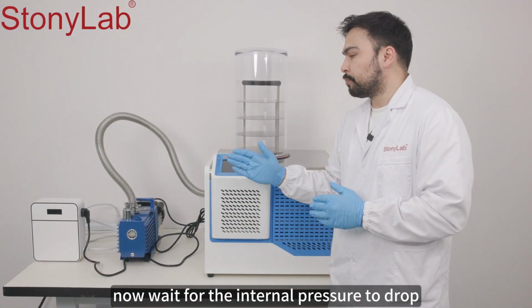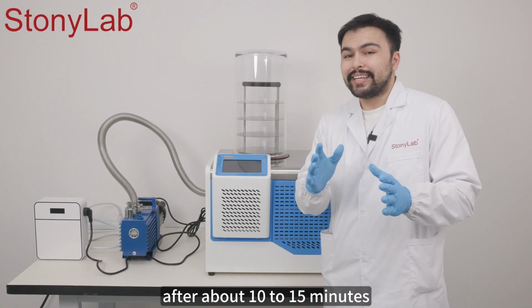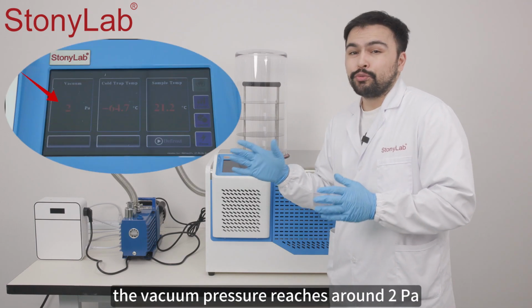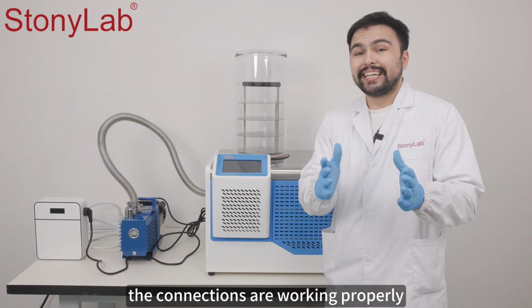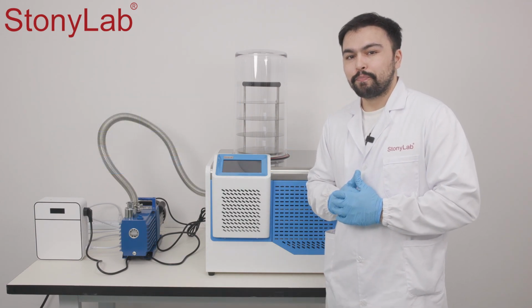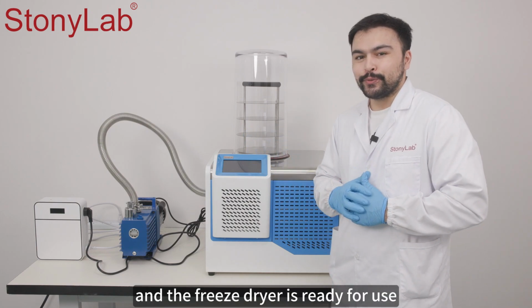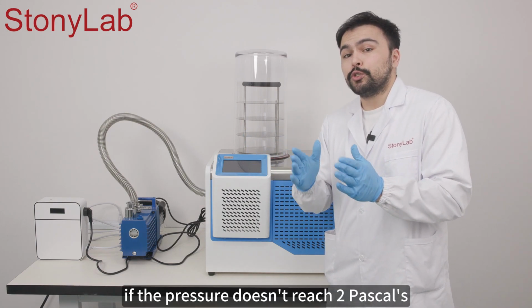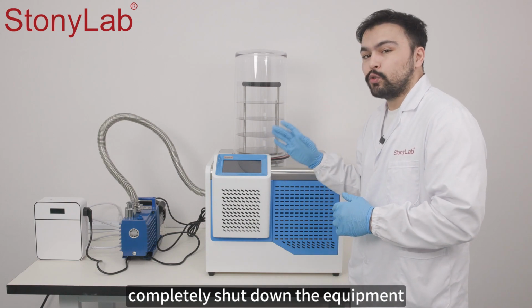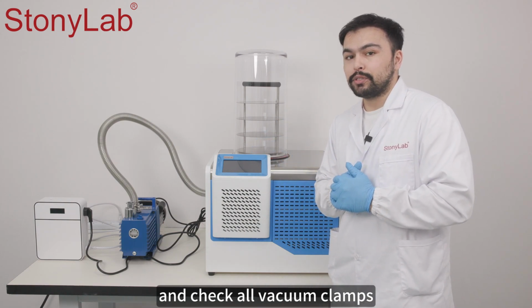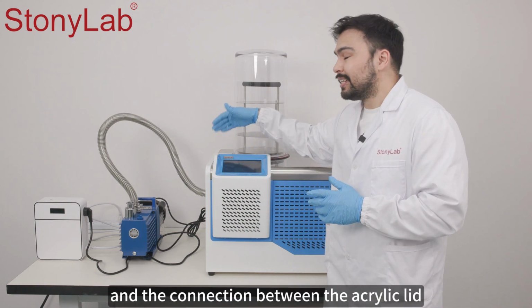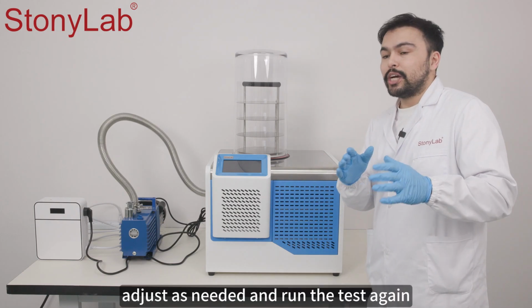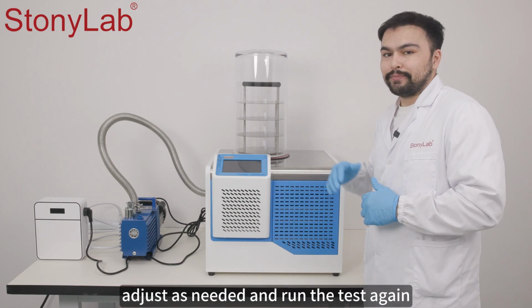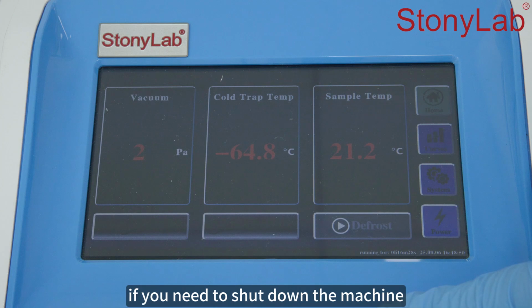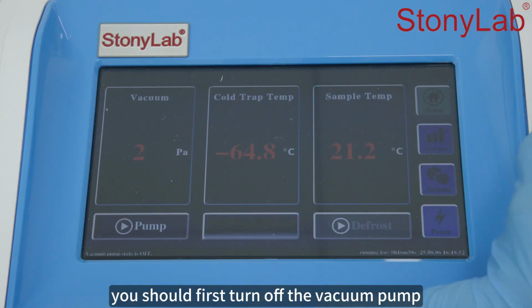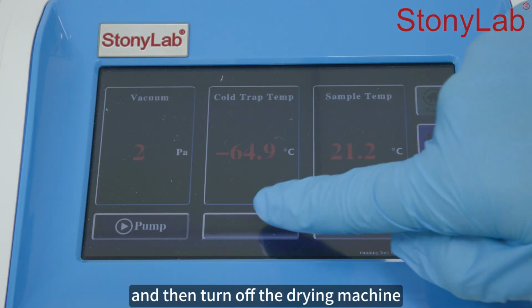Now, wait for the internal pressure to drop. After about 10 to 15 minutes, the vacuum pressure reaches around 2 pascals, the connections are working properly, and the freeze dryer is ready for use. If the pressure doesn't reach 2 pascals, completely shut down the equipment and check all vacuum clamps and the connection between the acrylic lid and the main unit. Adjust as needed and run the test again. If you need to shut down the machine, you should first turn off the vacuum pump and then turn off the drying machine.